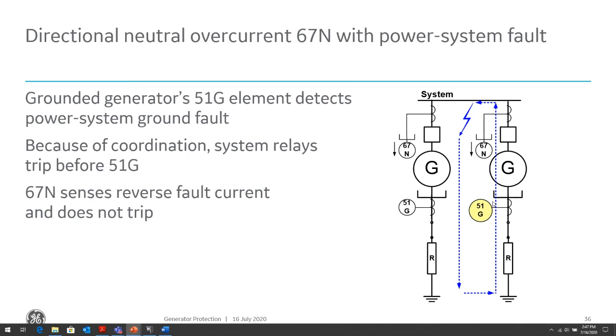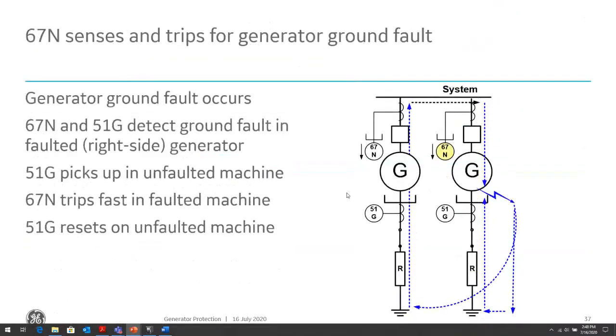So if there is a fault within the generator, the 67N on that generator will see that fault, whereas the 67N on the unfaulted generator will not see any ground fault, because it only sees ground faults flowing outside of the generator and blocks from operating, since it's only looking for faults in its generator protection zone. So the 67N senses current direction and will not trip for an external fault, whereas for an internal fault, it will sense current in the forward direction and trip only its generator breaker. So it helps discriminate between faults on those two generators.